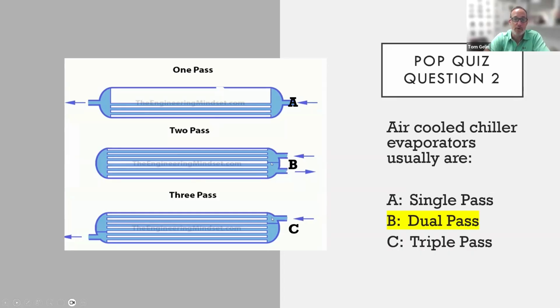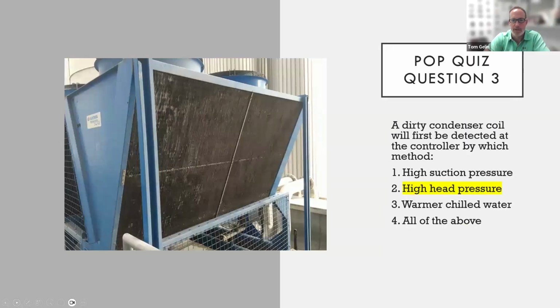Air-cooled chiller evaporators are usually dual pass because you want the piping on the same side, since you may not have access to piping on both sides. Does this ever deviate, Ahmad? For an air-cooled chiller, it's always dual pass - always in and out on the same side, correct? It depends - if you're using DX or flooded, it can be from the same side, but it depends on the length and the diameter. Right, because some of your air-cooled chillers have flooded heat exchangers, and we're going to talk about that a little bit later. Okay, next one - everybody needed to think about this one, right?